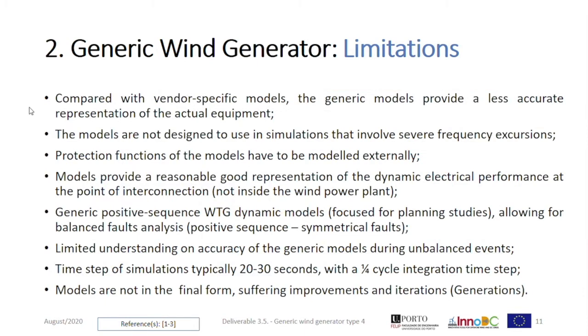Here are listed some of the main known limitations of the generic wind generator models. There are discussions about the appropriateness of generic models due to accuracy loss compared to vendor-specific equipment; however, this will depend on what is acceptable for the study being conducted. Further limitations are that the models are not designed for simulations involving severe frequency excursions, and protection functions must be modelled externally. The models provide a reasonably good representation of dynamic electrical performance at the point of interconnection, not inside the wind power plant. There is limited understanding of accuracy during unbalanced events, and the simulation time step is typically 20 to 30 milliseconds. Finally, models are not in their final form, undergoing improvements and iterations — or generations — as mentioned at the beginning.